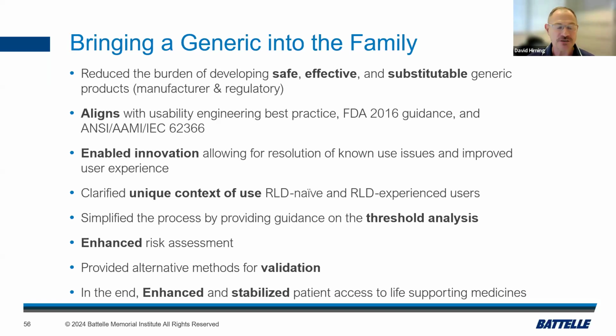The methodology that we're putting forward aligns with usability engineering best practice. It aligns with FDA 2016 guidance, and it aligns with IEC 62366. We've enabled innovation, allowing for resolution of known use issues and improved user experience.